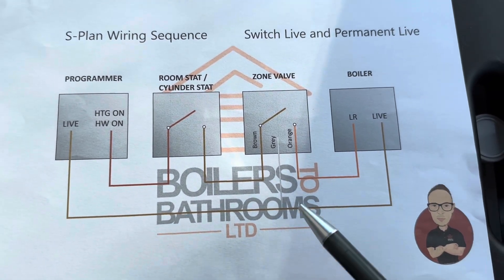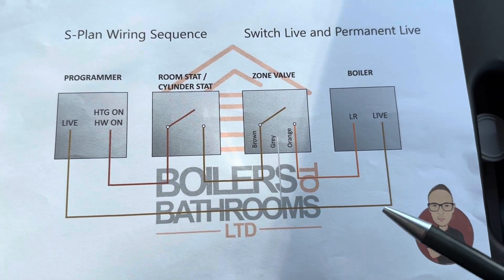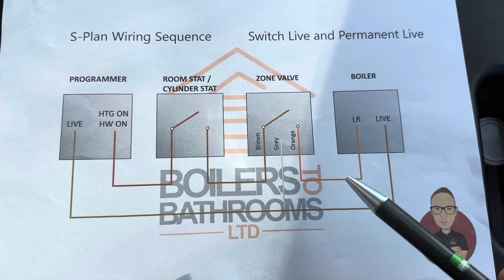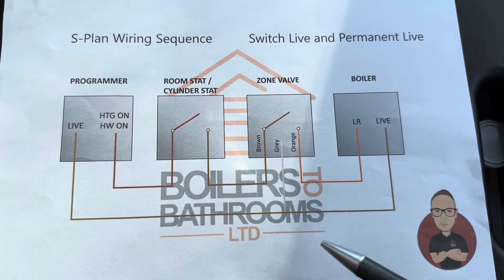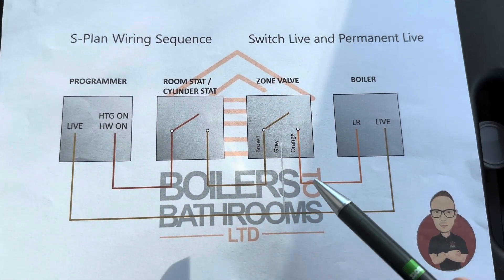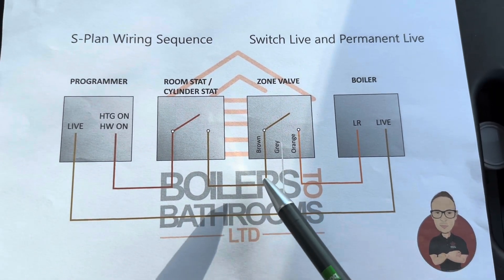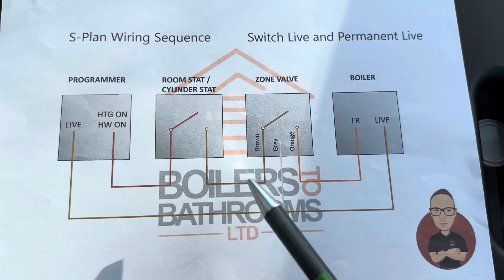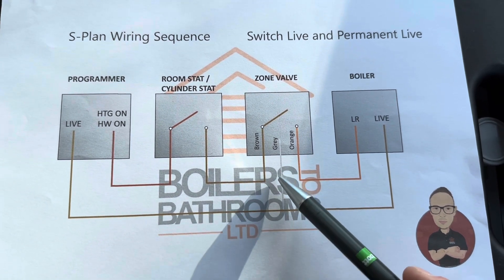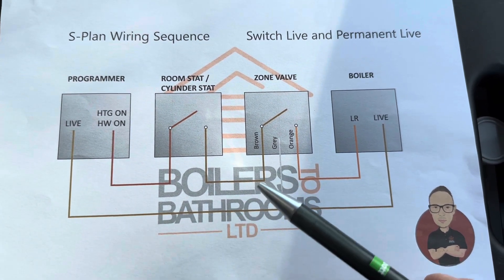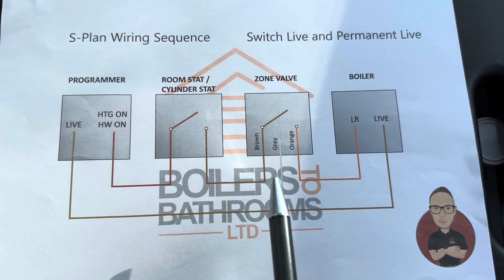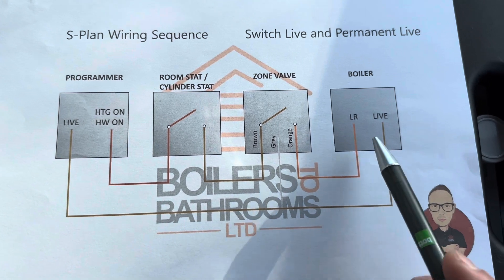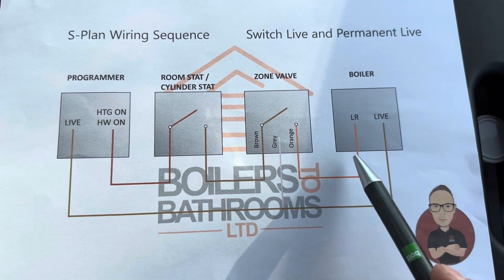With breakdowns it's all about localizing the area you're going to work in. The point of going to the 10-way is that it's almost like a mid-section — you can test to see whether we're going one way to check external controls or the other way to check the boiler. So: is it a boiler fault or is it an external controls fault?